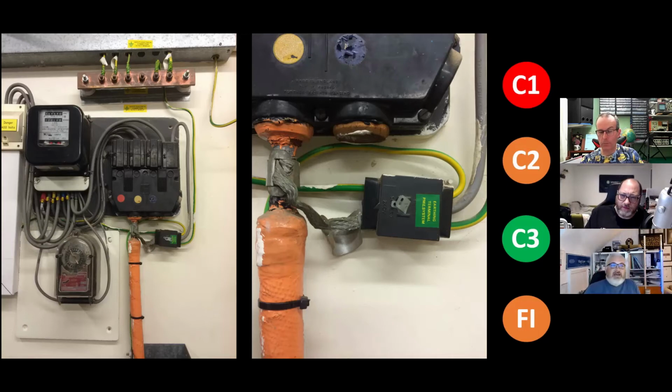Effectively, yes. However, just to throw something more in there, if you have neutral currents, by doing that you can create circulating currents on your network. Yeah, that's not a good idea. That can easily be solved by insulating that part of the cable. So the problem is the supply cable has exposed metallic parts. Effectively, yes. So if they covered that up, that would get rid of that problem. Well, if you think about what a PILC cable is constituted as, the supply conductors, the neutrals and the lives are very well insulated from the sheath.